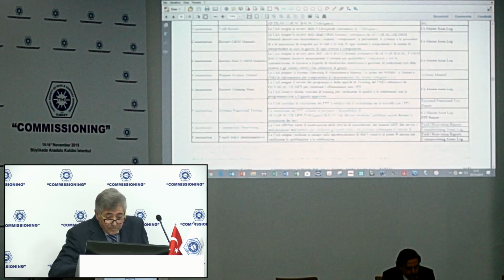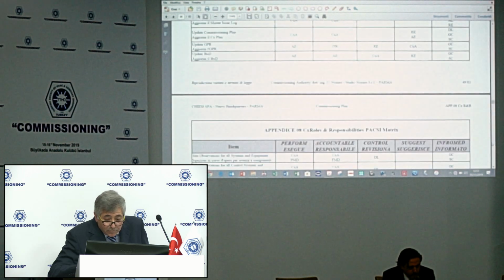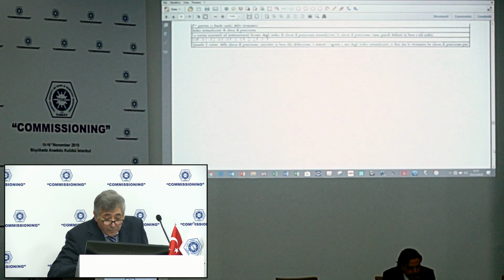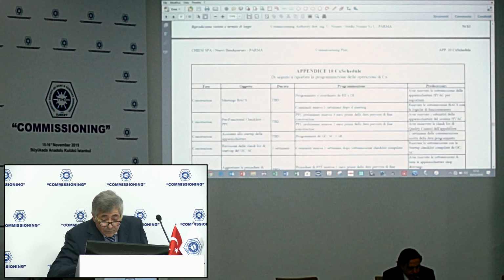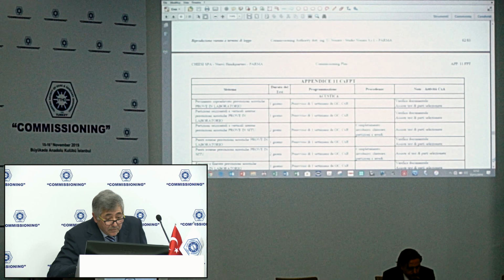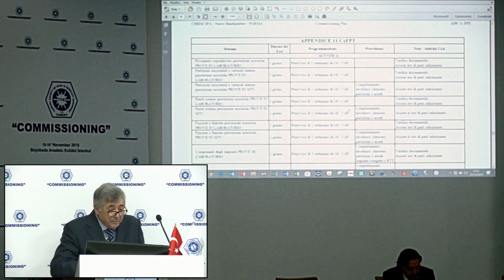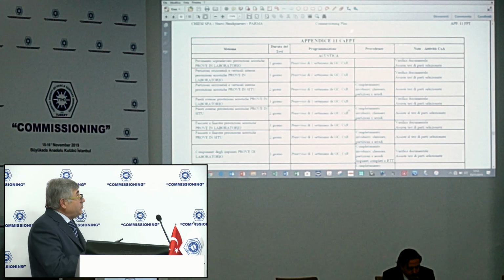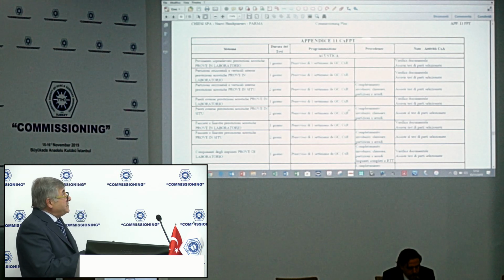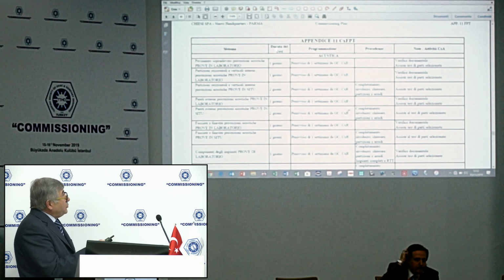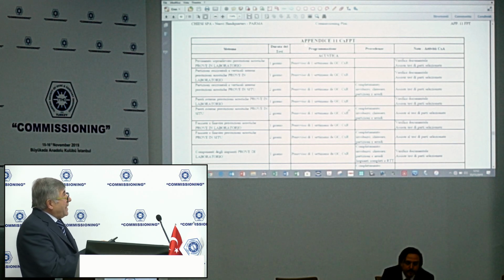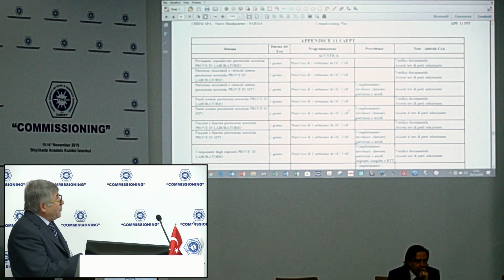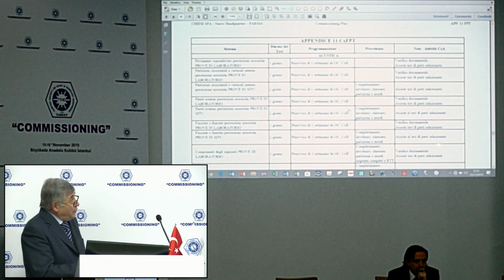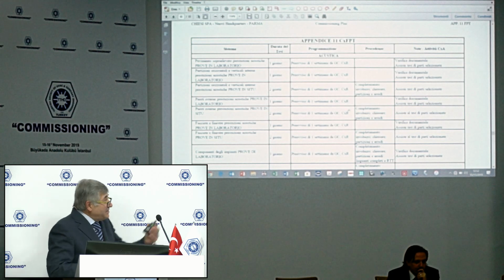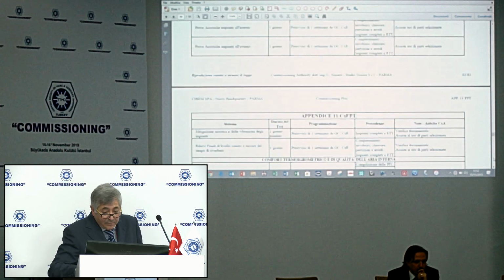We don't have too much time for the full procedure, so let's go directly to appendix 11. This is the schedule, the proposal for the schedule of the functional performance test: the duration of the test, which kind of schedule, for example one week, the predecessor, and the activities of the commissioning authority, all listed in the commissioning plan.